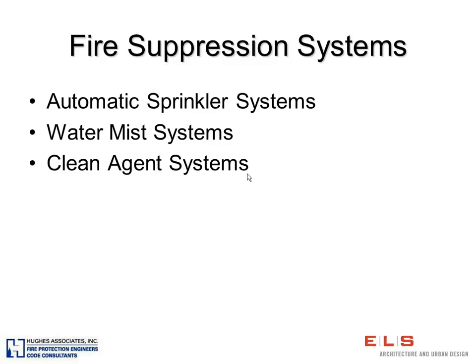Many of you may have heard of the term halon systems. We no longer use halon because it's an ozone-depleting chemical, and so we have several halon replacement type clean agents that we use. They are essentially gaseous agents that can extinguish a fire without damage to the contents of your building.